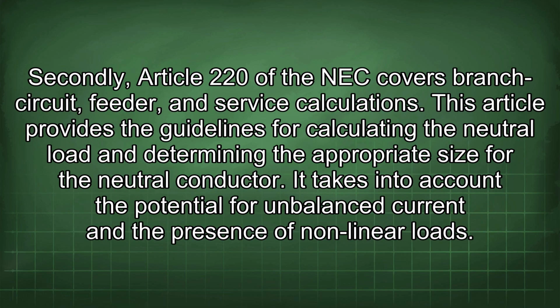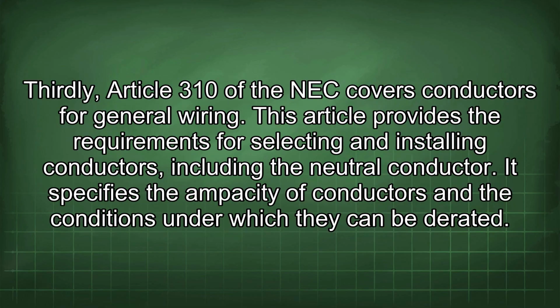Secondly, Article 220 of the NEC covers branch circuit, feeder, and service calculations. This article provides the guidelines for calculating the neutral load and determining the appropriate size for the neutral conductor. It takes into account the potential for unbalanced current and the presence of nonlinear loads. Thirdly, Article 310 of the NEC covers conductors for general wiring.